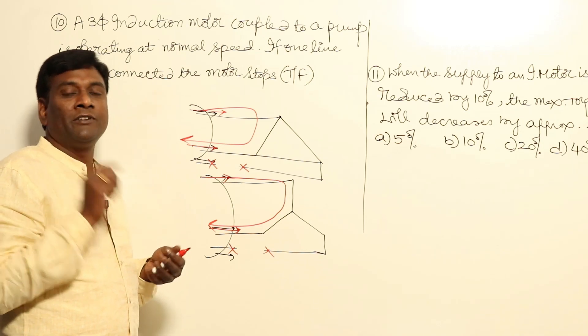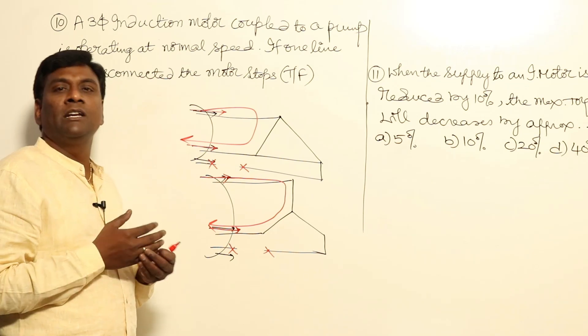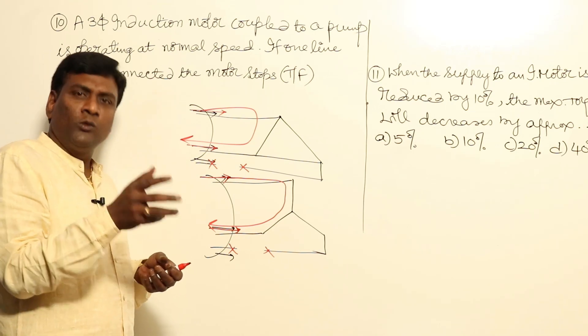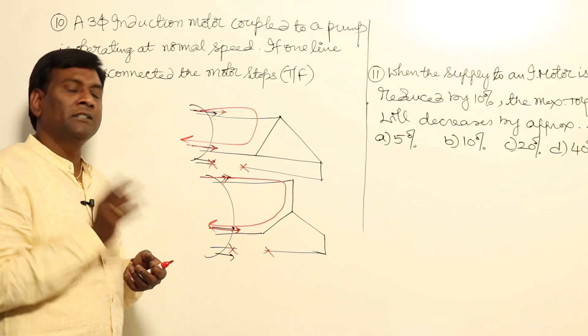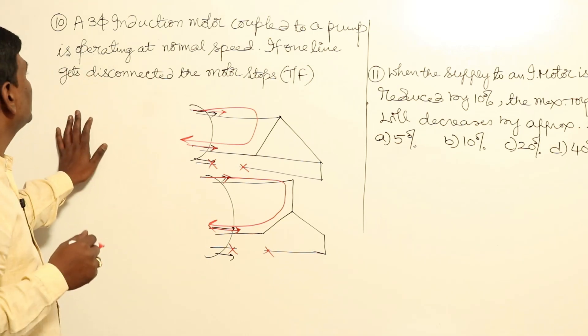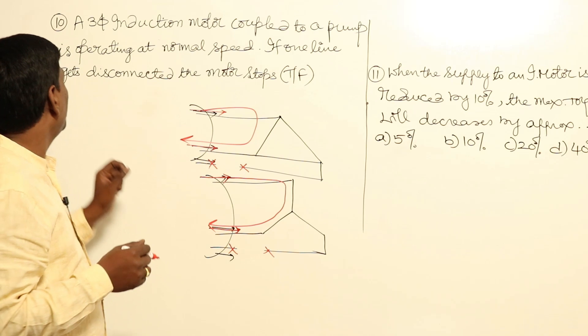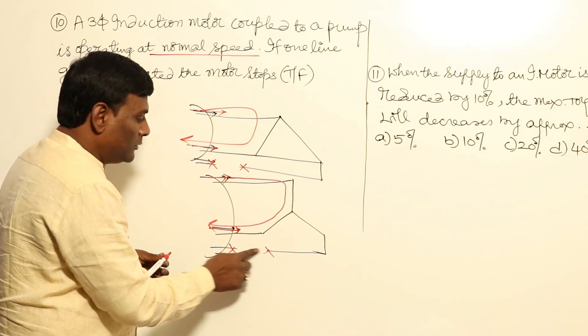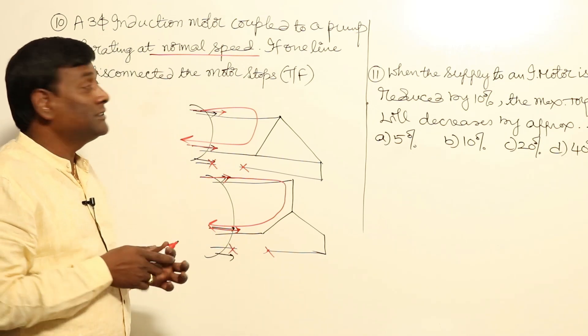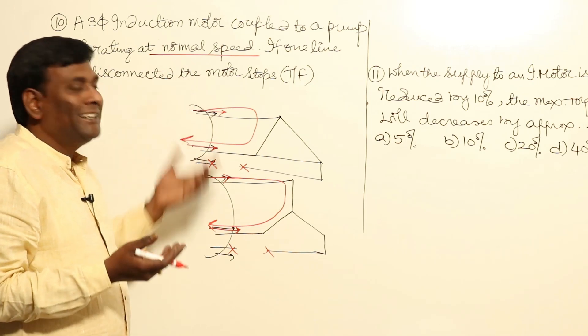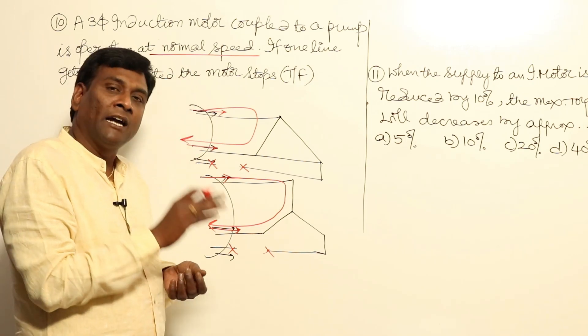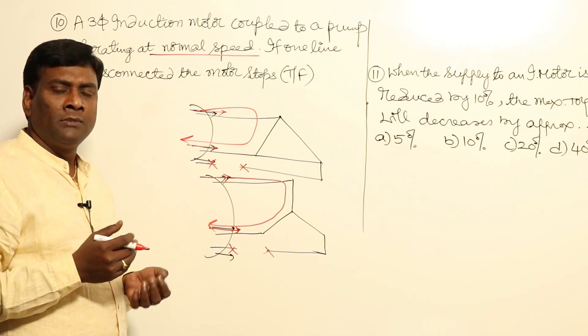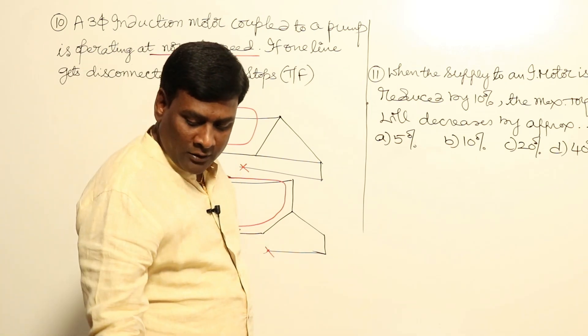So out of three phases, if one phase fails, it will become a single-phase motor. A single-phase motor does not have its own self-starting capability, but if you rotate it in one direction it will continue to operate in the same direction. In this question, the motor is already operating at normal speed, so when one phase blows it becomes single-phase but is already rotating — it will continue to rotate, of course at reduced speed or increased slip.